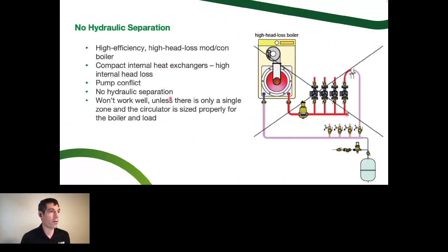So let me talk a little bit about if we didn't do any of this, if we just connected those two pipes straight across. In that last slide, we don't address anything. In this scenario, and this is pretty common down in the States, I think that you guys in Canada do a better job of paying attention to some of the new technologies and things that need to change with the heat emitter options and energy source options, like new modulating condensing boilers and heat pumps and things like that. There are a lot of places in the States where the least expensive way to replace a cast iron boiler that may have failed is to just put in a mod con and not change anything else. Just put a couple unions in there to make it easy for yourself, but then you're off and running.